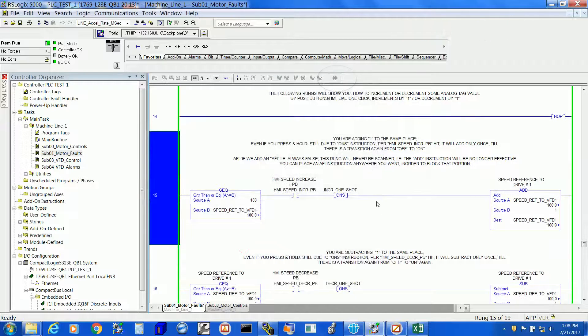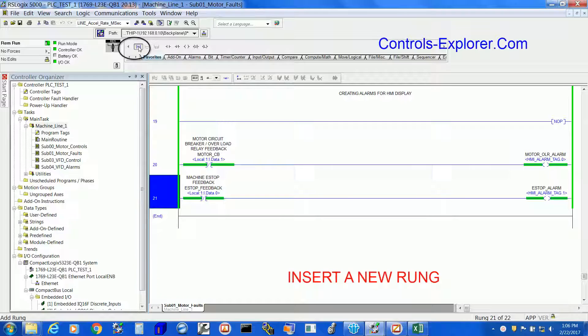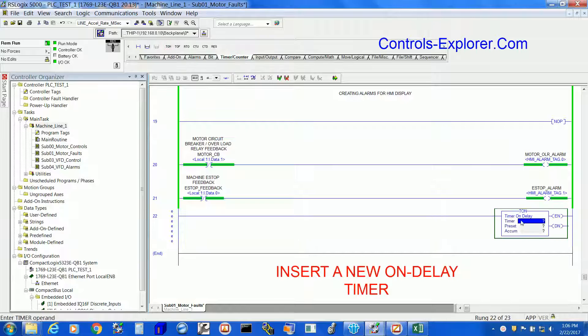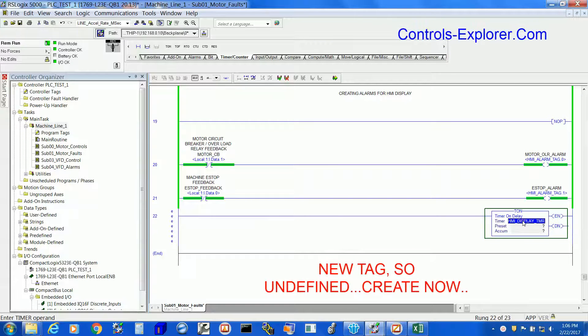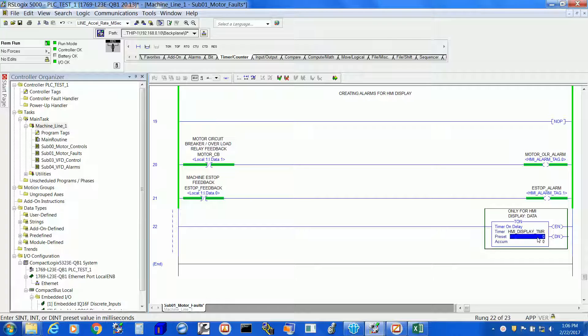Next, we are going to add new rungs as well as create new tags in the latter part of it. We are now creating a new rung and we will insert a timer. Select timer counter, T on delay, and type the tag name for this timer. Remember, this is a brand new tag, so it's undefined. Right click, new HMI timer, write a description, then create it. The PLC now recognizes this tag.